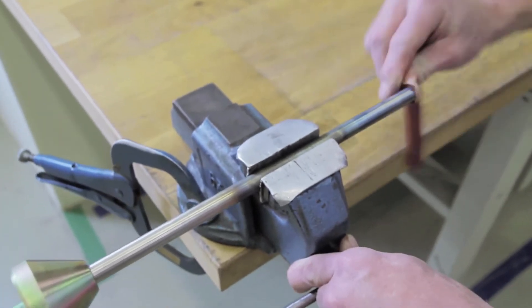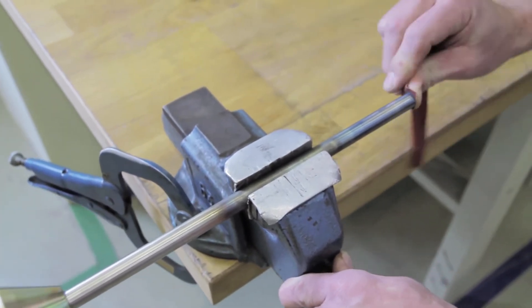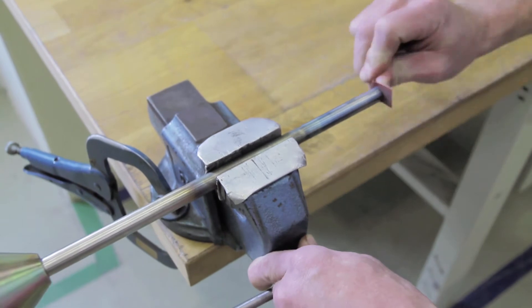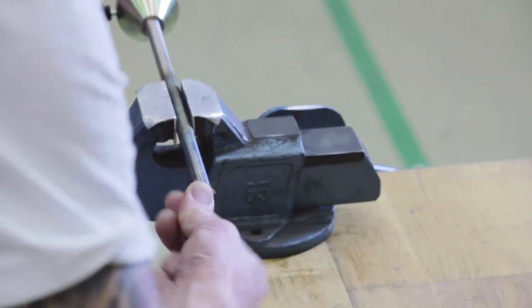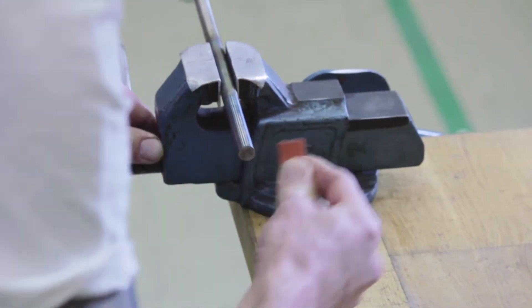By grinding off the oxide from your probe, you don't need to consider influence from the oxide layer. Start with the probe tip. Press a piece of emery paper against it with your thumb and rotate back and forth until the oxide is removed.